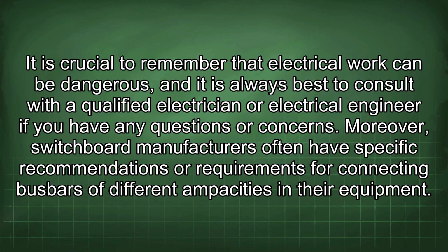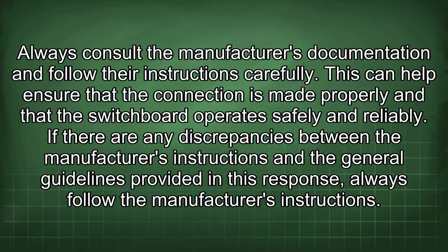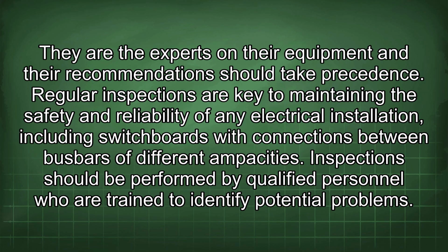Moreover, switchboard manufacturers often have specific recommendations or requirements for connecting busbars of different ampacities in their equipment. Always consult the manufacturer's documentation and follow their instructions carefully. This can help ensure that the connection is made properly and that the switchboard operates safely and reliably. If there are any discrepancies between the manufacturer's instructions and the general guidelines provided in this response, always follow the manufacturer's instructions. They are the experts on their equipment and their recommendations should take precedence.